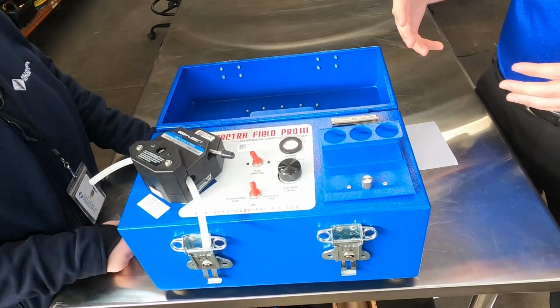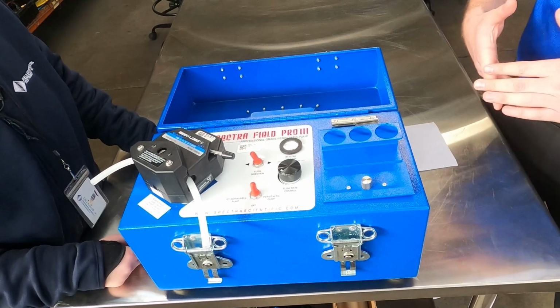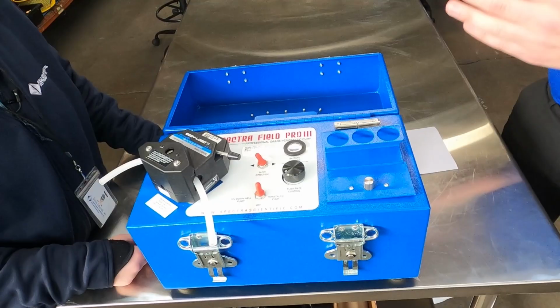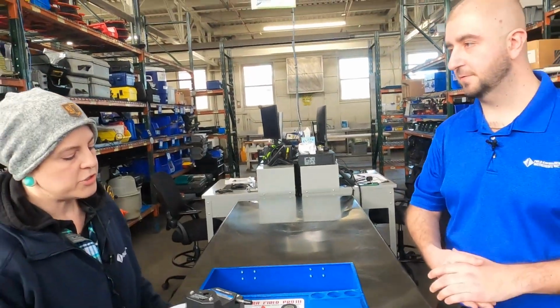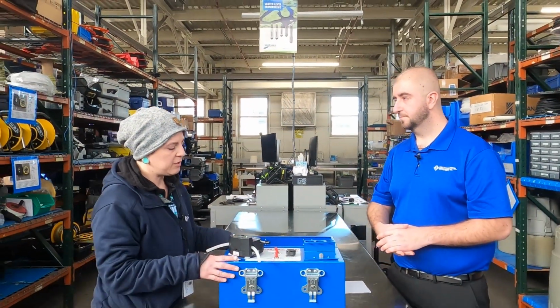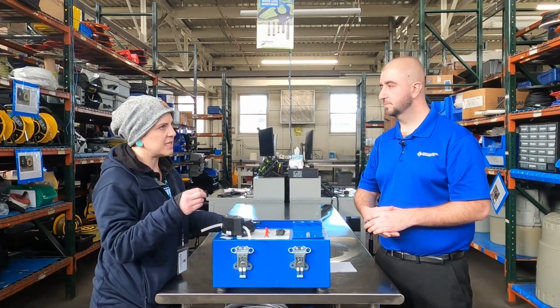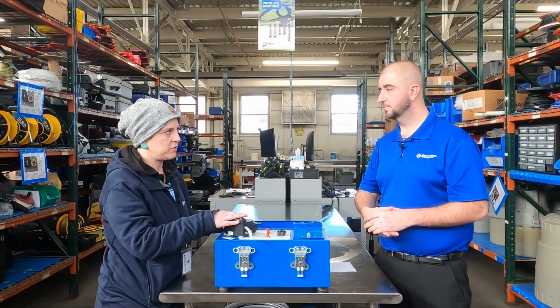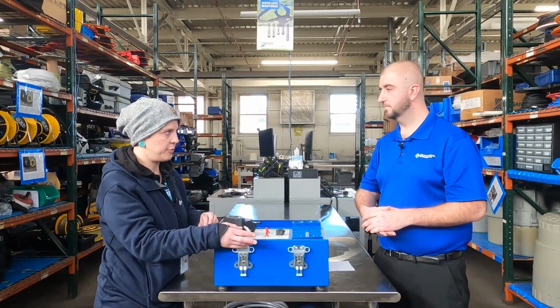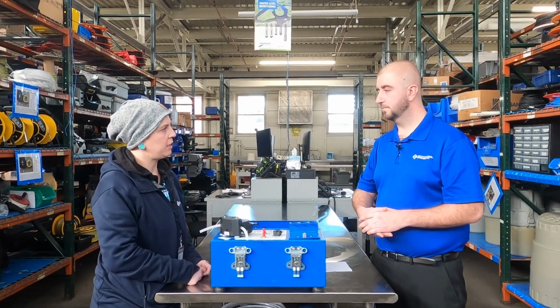You mentioned not going more than 25 feet - why is that important for this application? For these peristaltic pumps, the head doesn't have enough power to force fluids through this tubing or hose, whatever you happen to be using.